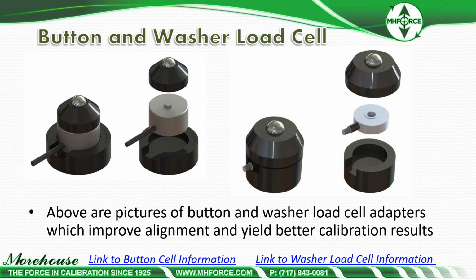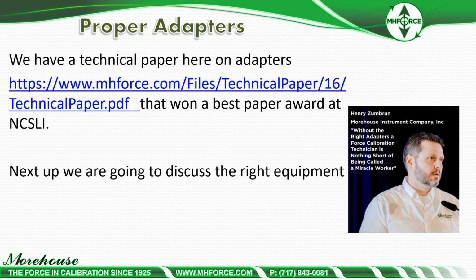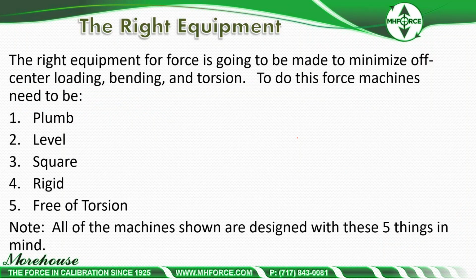Above are pictures of button and washer load cell adapters, which can improve alignment and yield better calibration results. We have a technical paper. Here's the link. It was one of the best paper awards at NCSLI. There was best overall, which it did not win, and there was best in category, which it won. I'm deeply honored to achieve that award for this paper because it matters. The paper was called "Without the Right Adapters, a Force Calibration Technician is Nothing Short of Being Called a Miracle Worker." That is so true.